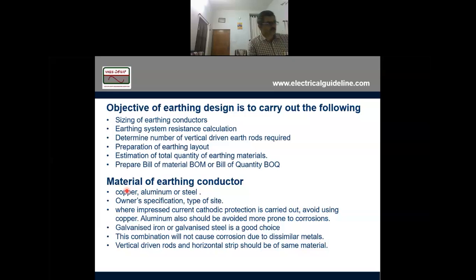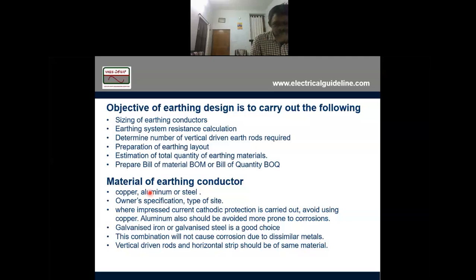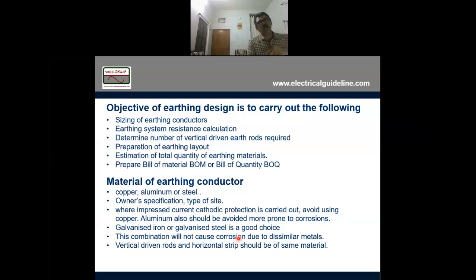Regarding the material to be used: it can be copper, aluminum, or steel. Copper cannot be used at cathodic protection areas. In certain places, aluminum is also not used — I will tell you later. The earthing material depends on the owner specification and type of site. Where we use impressed current protection, we cannot use copper. Galvanized iron and galvanized steel are good. Above ground and below ground — that also we should be very careful about, and I will explain that too.